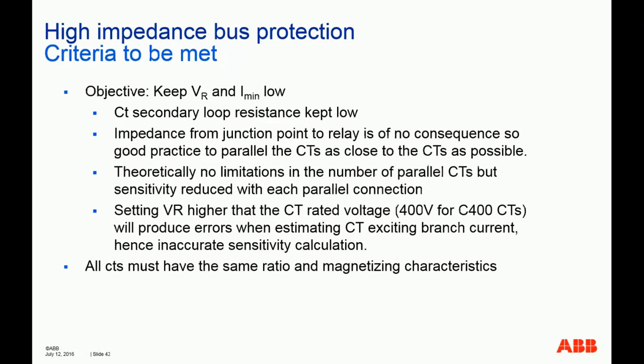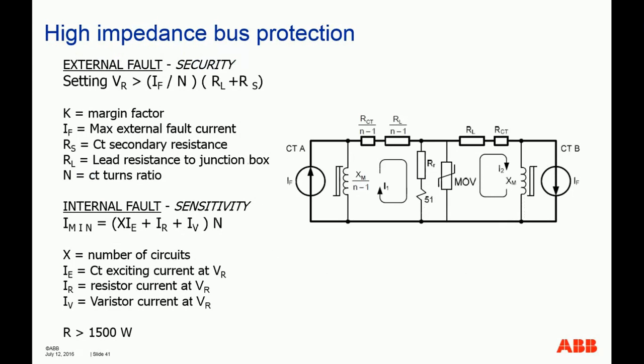Some criteria need to be met for high impedance bus protection. When we calculate the voltage here, we can calculate according to the application guide that I just mentioned, based on the resistor here. So what if you have a very big resistor? This RL, again, remember, is the CT lead. CT lead means the resistance of the CT wires from the CT terminal junction box back all the way to the relay room. These are your lead resistance.